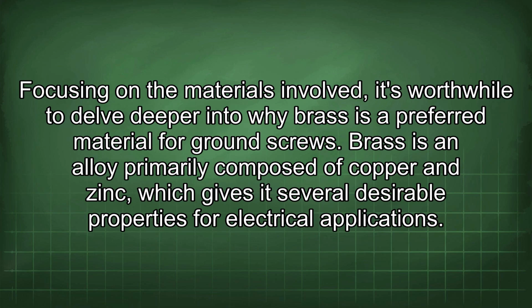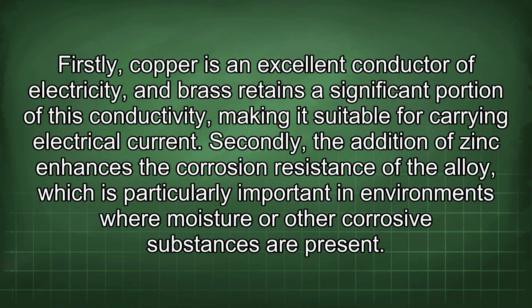Focusing on the materials involved, it's worthwhile to delve deeper into why brass is the preferred material for ground screws. Brass is an alloy primarily composed of copper and zinc, which gives it several desirable properties for electrical applications. Firstly, copper is an excellent conductor of electricity, and brass retains a significant portion of this conductivity, making it suitable for carrying electrical current. Secondly, the addition of zinc enhances the corrosion resistance of the alloy, which is particularly important in environments where moisture or other corrosive substances are present.